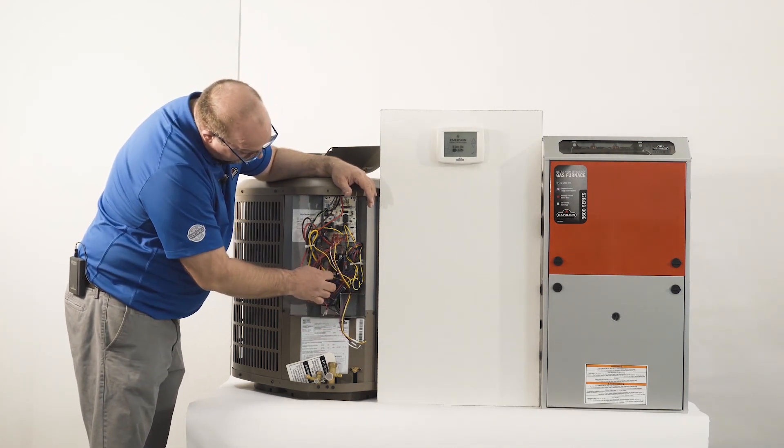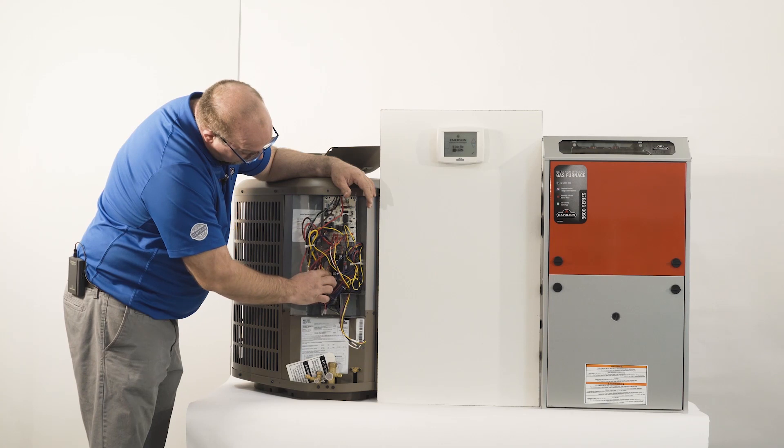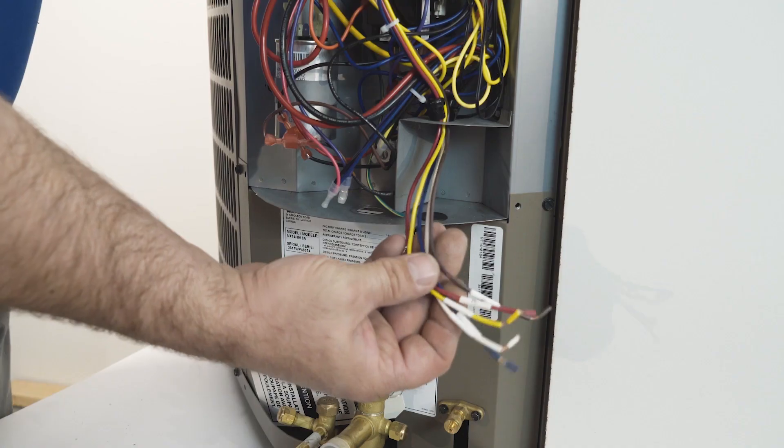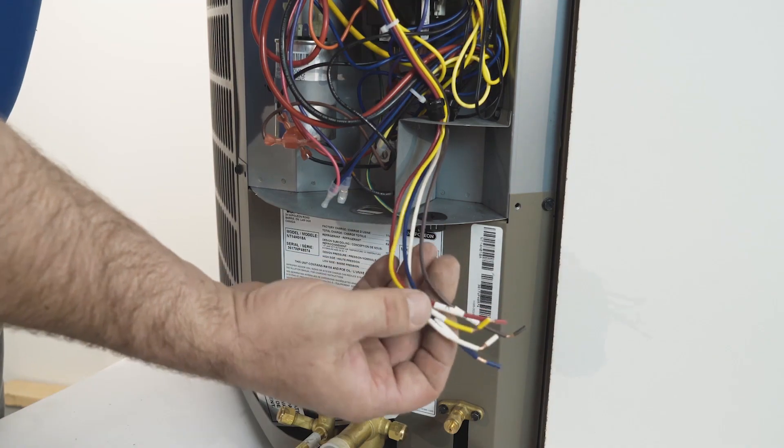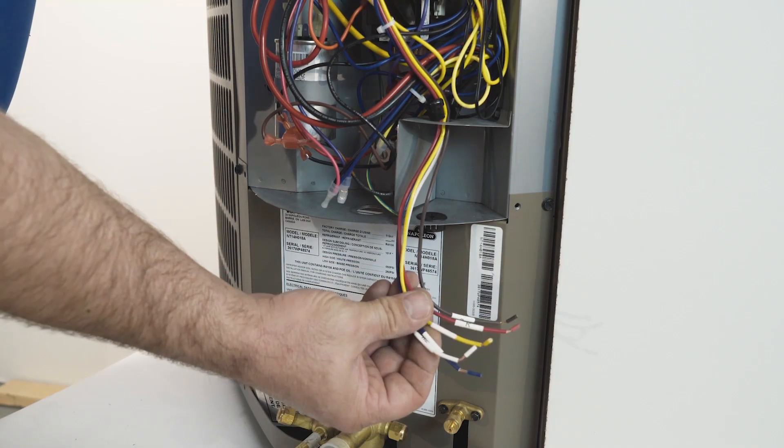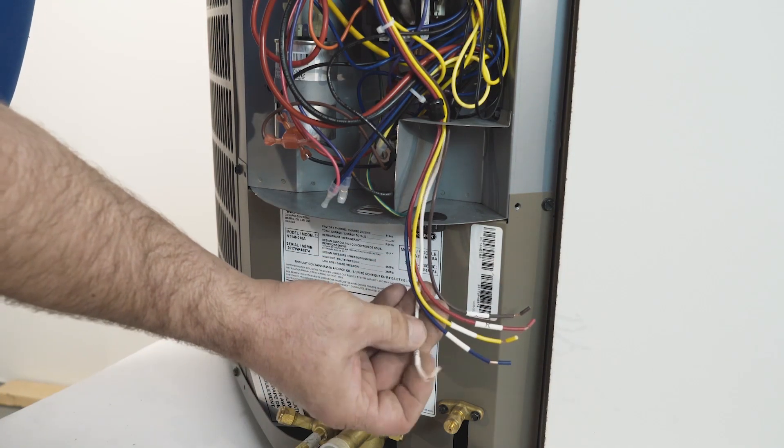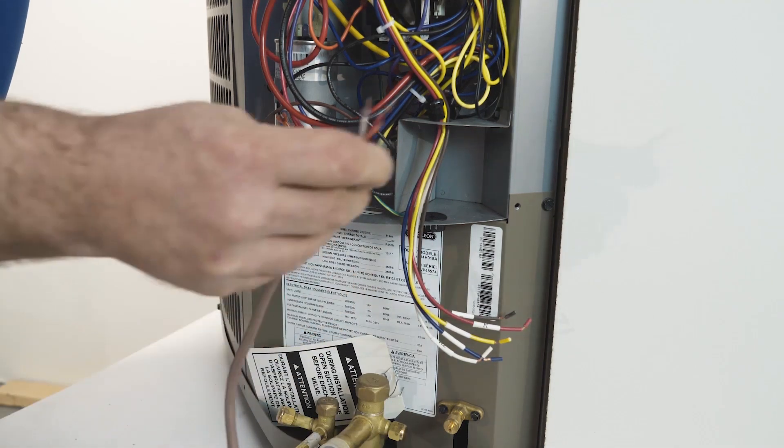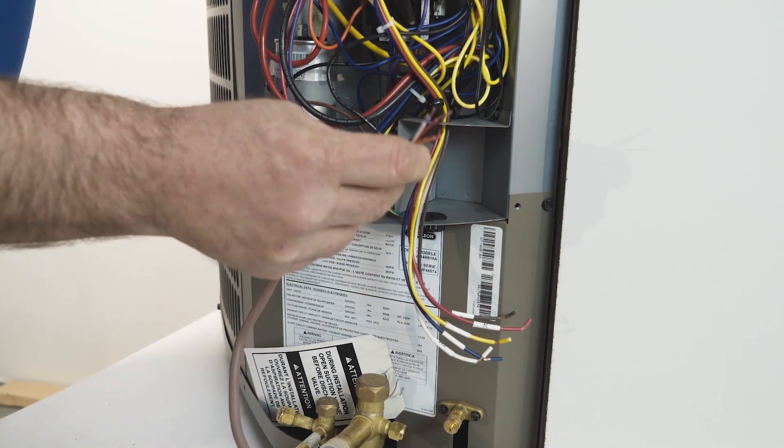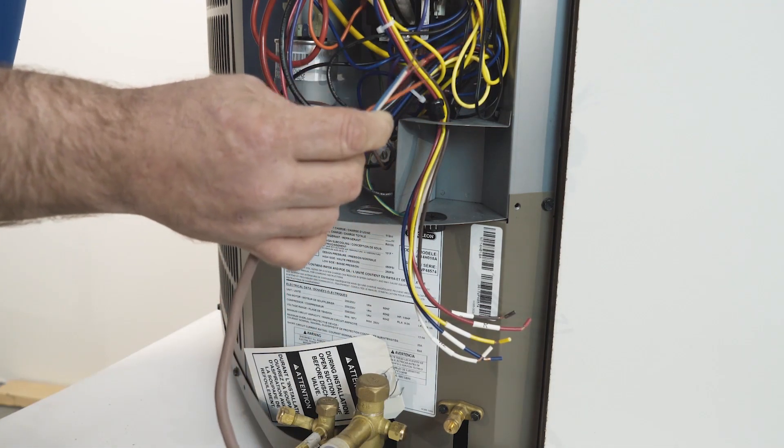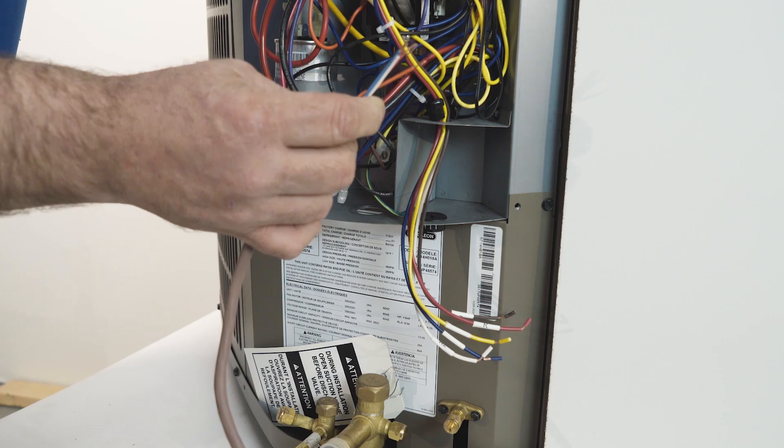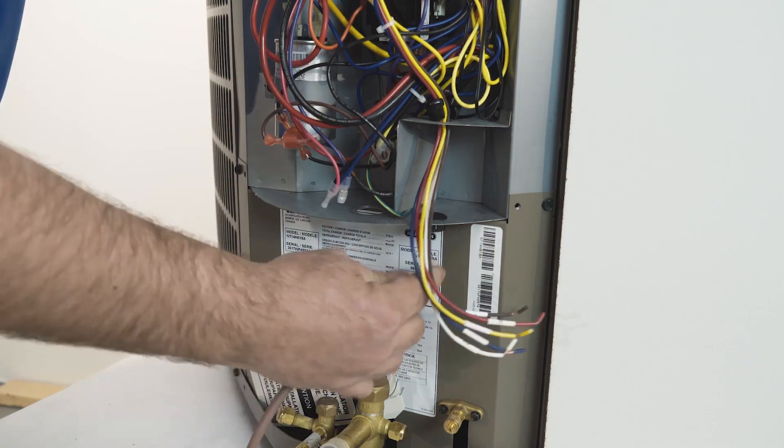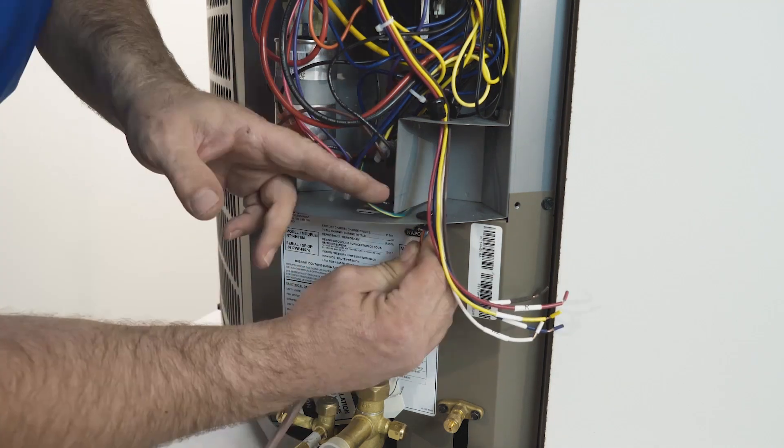The high voltage connections are on the contactor here. The low voltage wire harness is labeled, so you bring your 18 minimum 5 wire from the furnace to the heat pump system.